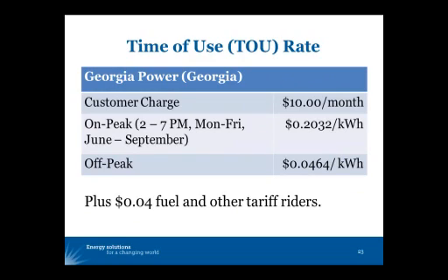There are several adders, including a fairly hefty fuel adder that applies to all of these, both these on-peak and off-peak rates. So that 4.6 isn't the whole thing. This utility is basically recovering the vast majority of its generation, transmission, and distribution costs in the on-peak rate, and only a small contribution to those costs in the off-peak rate. It should be pretty effective at getting people to leave their thermostats higher until 7 p.m. and to shift their laundry into nights and weekends.